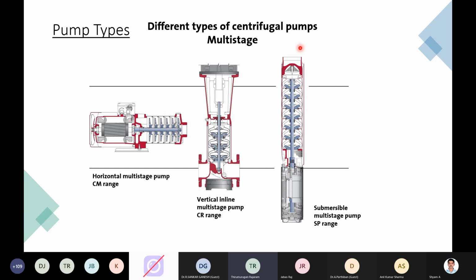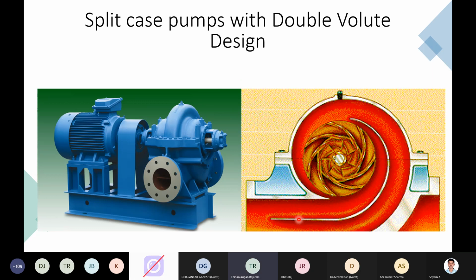And these are submersible borewell pumps. If you have a lot of borewells for water intake application, obviously these submersible borewell pumps are multi-stage, which can work even close to 30 bar pressure operation also. And of course, there are very large vertical turbine pumps, mainly used in MCW, meaning your raw water intake, and even for large cooling tower applications it is used. Okay. And then your split case pumps for large flows, say up to even 10,000 cubic meter capacities, you are able to offer these split case pumps.